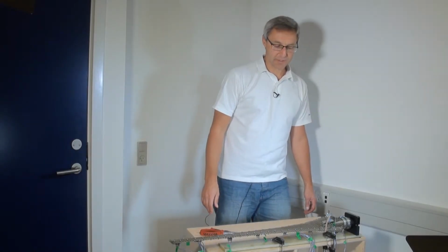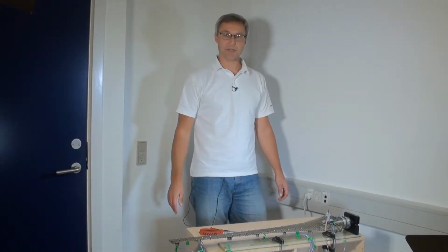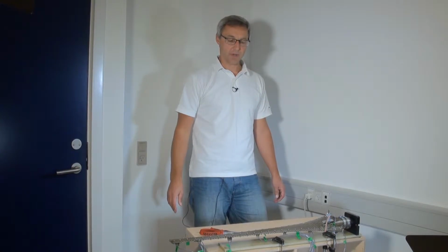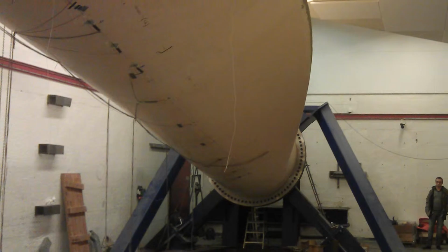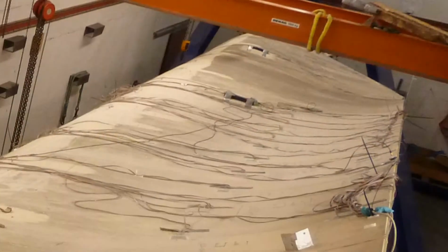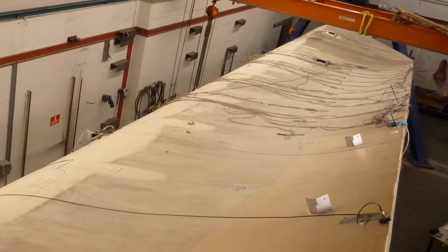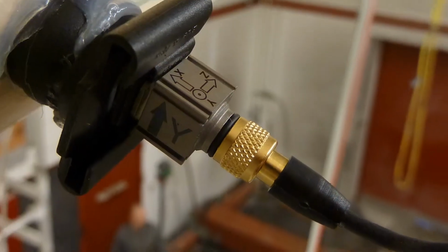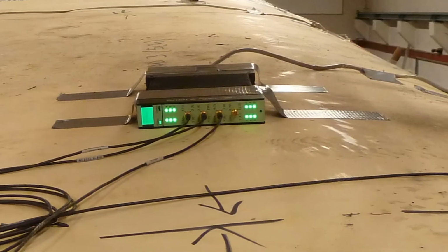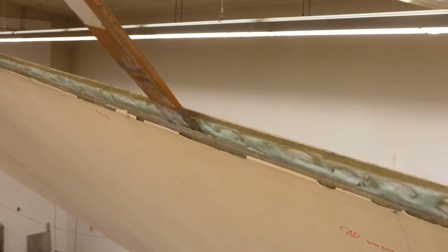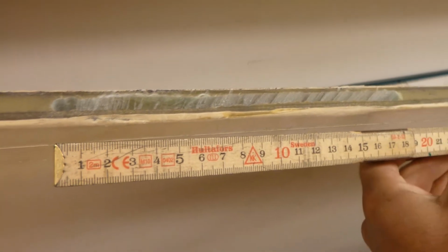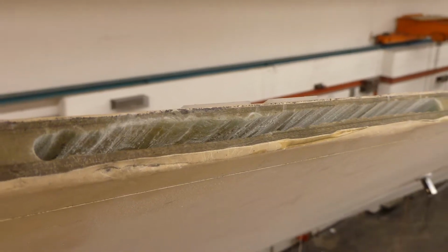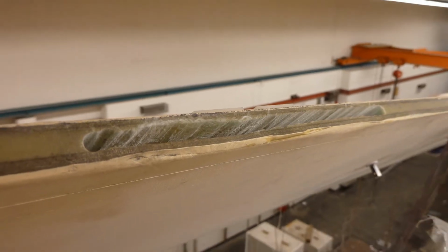Since 2011, Brüel & Kjær has led and participated in a project called Predictive Structural Health Monitoring of Wind Turbine Blades. In the frame of this project, we made a lot of experiments, aiming to develop a technology able to detect and localize damages on wind turbine blades. We developed technology that is able to detect even a 20 centimeter damage on a 34-meter blade in the presence of realistic noise.